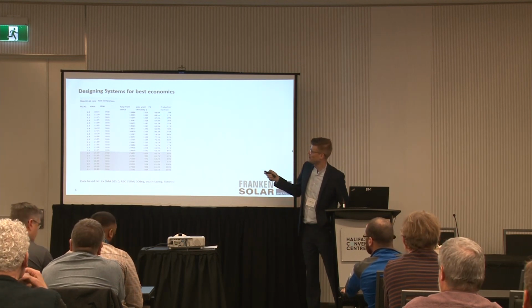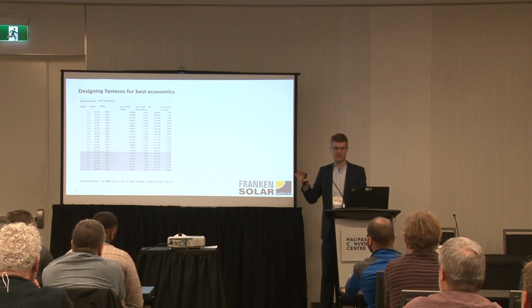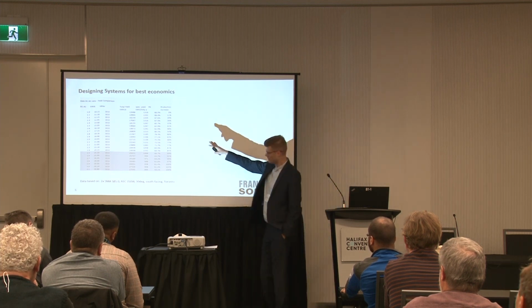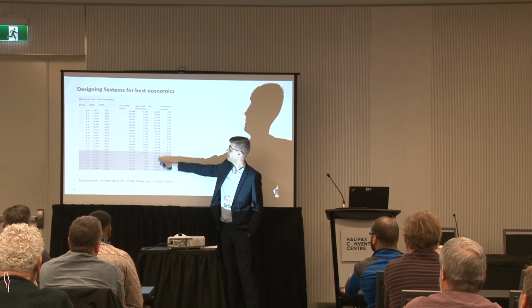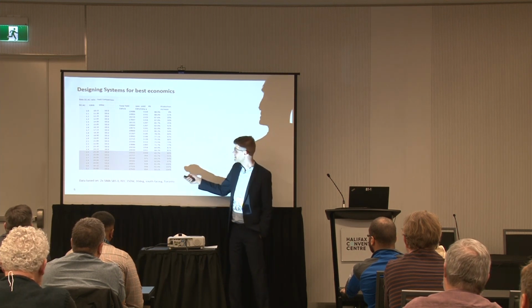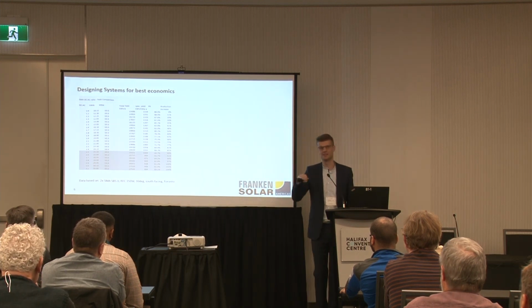Yep. So here, for example, we have, at perfect conditions, a performance ratio of 88%. That's, in a real-life scenario, already very good. Most systems operate probably at 80% as a good operation point. The more oversizing you have, the lower that PR ratio will go, all the way down to about 60%. And the delta between the 60% we have here and the 88% is exactly your clipping loss. Or if you look into, that's probably easier to handle, the specific yield in kilowatt hours. What used to be, let's say, a 1300 kilowatt hour per kilowatt peak system is now becoming just a 900. So the efficiency is going down based on the inverter being at its max and not being able to use the excess power.